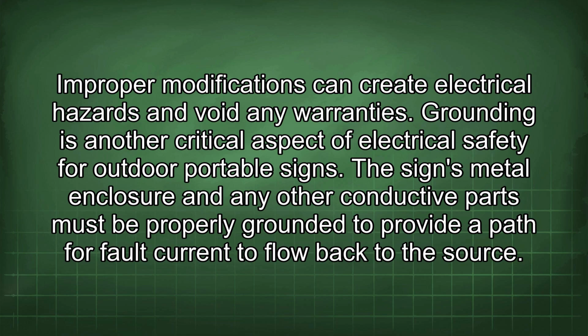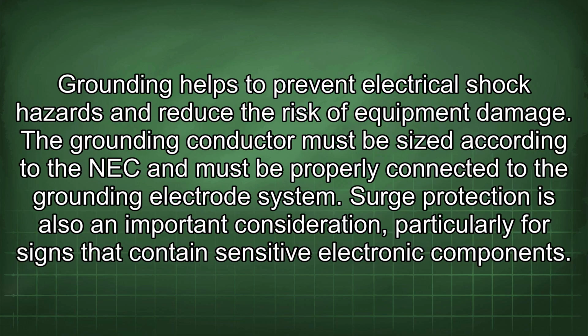Grounding is another critical aspect of electrical safety for outdoor portable signs. The sign's metal enclosure and any other conductive parts must be properly grounded to provide a path for fault current to flow back to the source. Grounding helps to prevent electrical shock hazards and reduce the risk of equipment damage. The grounding conductor must be sized according to the NEC and must be properly connected to the grounding electrode system.